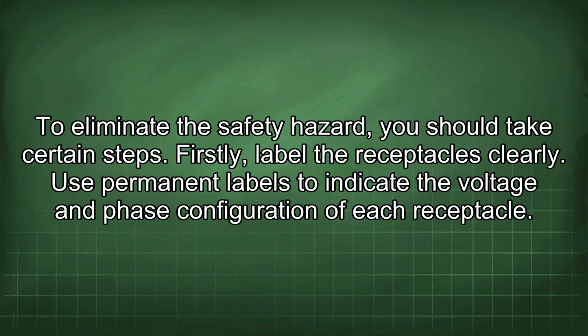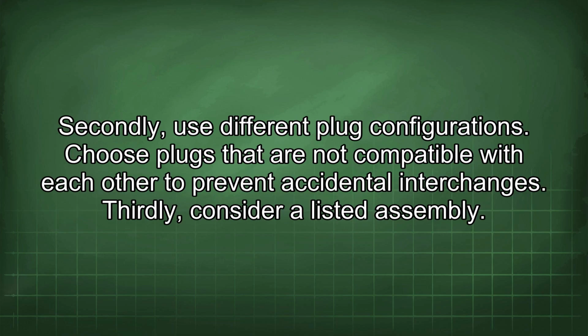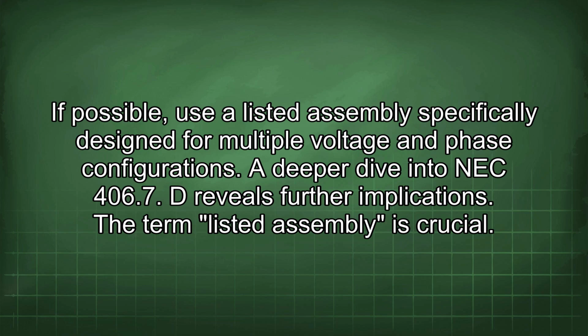To eliminate the safety hazard, you should take certain steps. Firstly, label the receptacles clearly. Use permanent labels to indicate the voltage and phase configuration of each receptacle. Secondly, use different plug configurations. Choose plugs that are not compatible with each other to prevent accidental interchanges. Thirdly, consider a listed assembly. If possible, use a listed assembly specifically designed for multiple voltage and phase configurations.